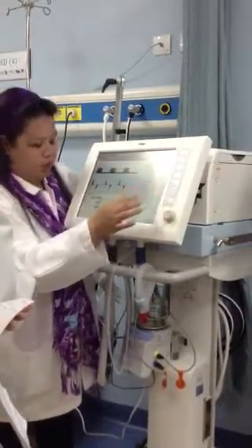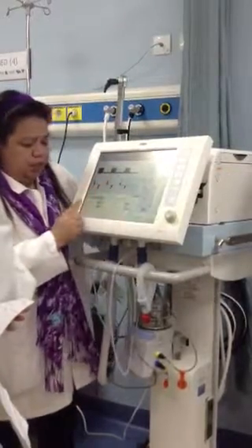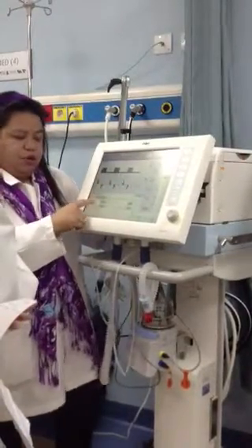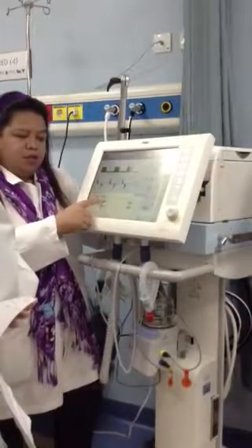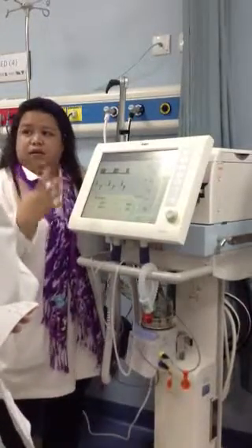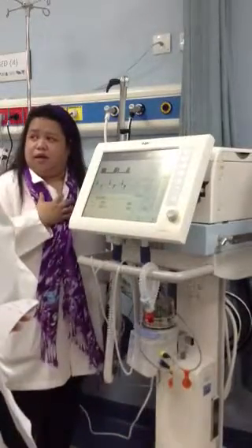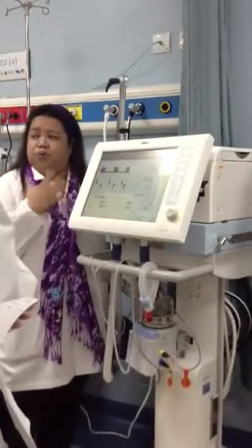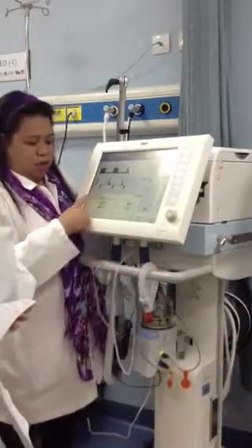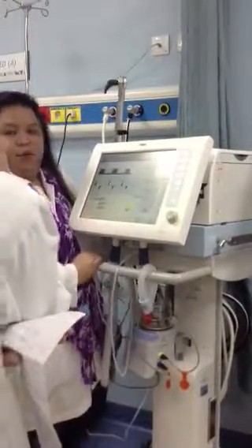For your special procedure, inspiratory hold is used if the patient needs to have an x-ray. Sometimes when we're doing x-ray, they're asking you to do breath holding. So this is the same use for them. And you can use your built-in nebulizer.